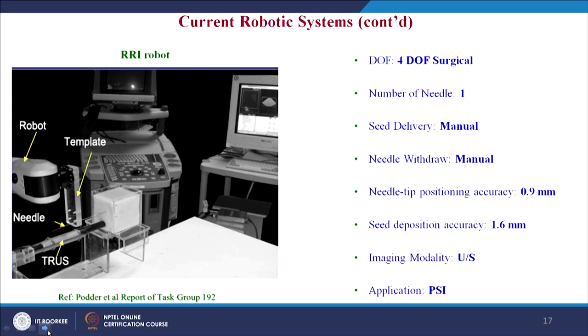The Robarts Research Institute (RRI), London, Ontario, Canada has developed a 4-degrees-of-freedom robotic system. The system supports the needle guide from the underside by two hinged parallelograms spaced such that their fixed points of rotation are mounted onto a common shaft. Needle tip positioning accuracy is 0.9 mm, seed deposition accuracy is 1.6 mm, and it involves a single needle.